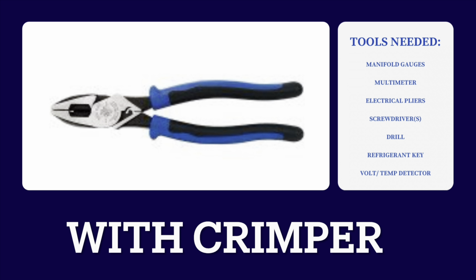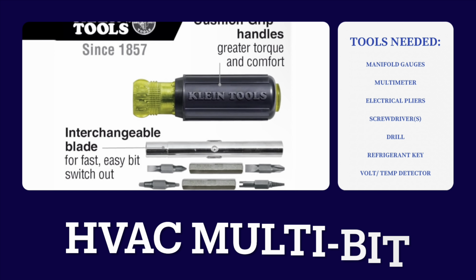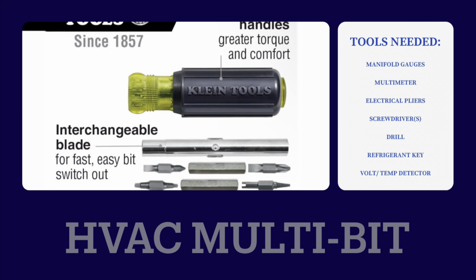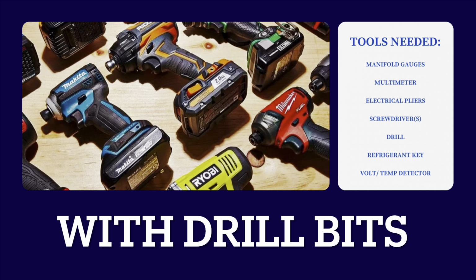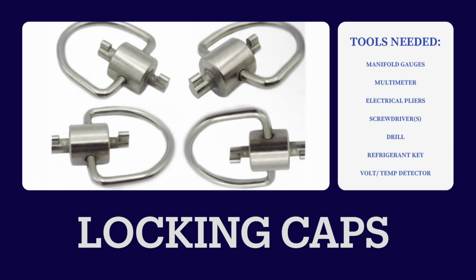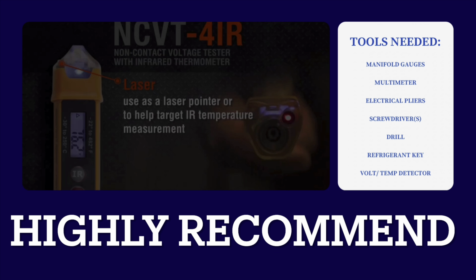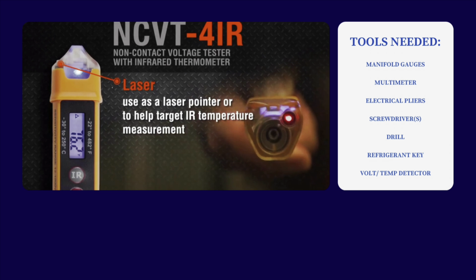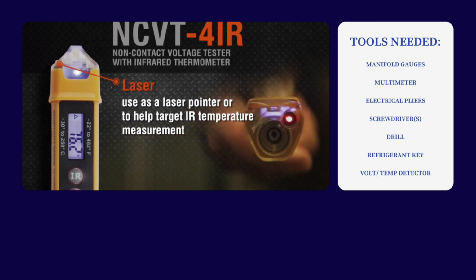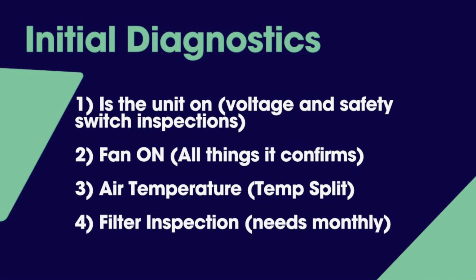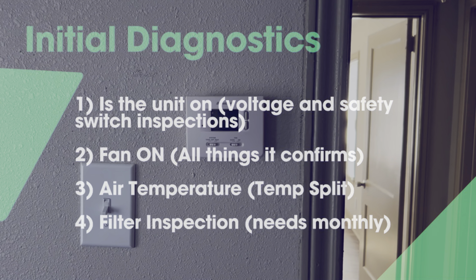electrical pliers, preferably with a crimper, a 6-in-1 or 11-in-1 screwdriver, a drill with drill bits, a refrigerant key to remove locking caps, and I highly recommend this voltage and temperature meter by Klein. Every service call should begin with these 4 steps. This will set you up to diagnose correctly what is wrong with the unit and move forward with the repair.